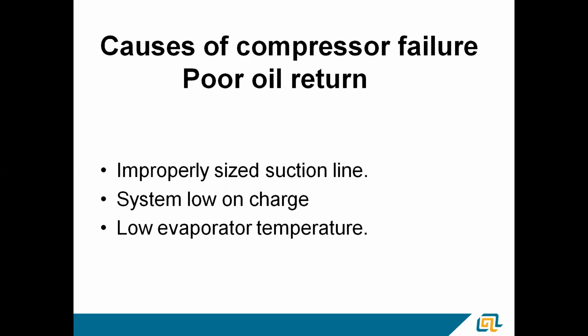So that's a good one to keep an eye on. Low evaporator temperature. If you're running that evaporator too cold, if the evaporator is starving for air, there's not enough air flowing across it, the evaporator temperature will drop and it will start logging oil in the evaporator. I'm sure we've all done it. You cut a liquid line off an evaporator, it's full of oil. That oil's just coming back on you. It makes a heck of a mess in the basement. That's an evaporator that was either run with not enough suction velocity or low evaporator temperature, allowing that oil to pool in there.